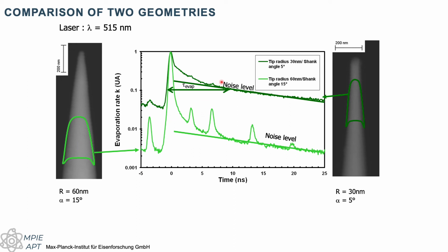And again, the time to go back to zero will change quite a lot. So there are many variables when we're using laser pulsing that might not have a reason at all when we're using voltage pulsing. Sometimes the mass resolution you need is this one and what you're getting is that one, and you don't really understand why. It's because your specimen is too small or too big, and it's not always that easy to control when we're preparing specimens.